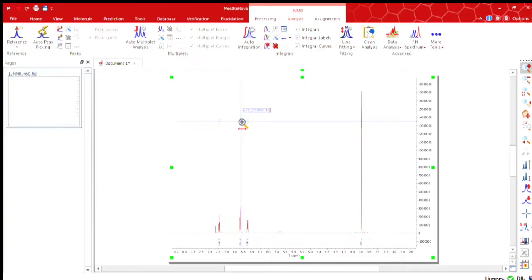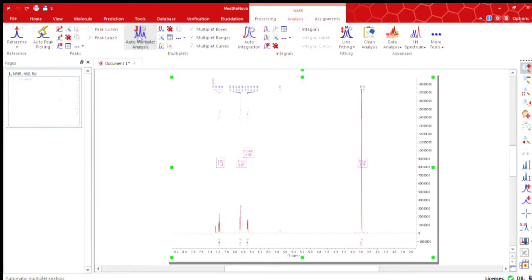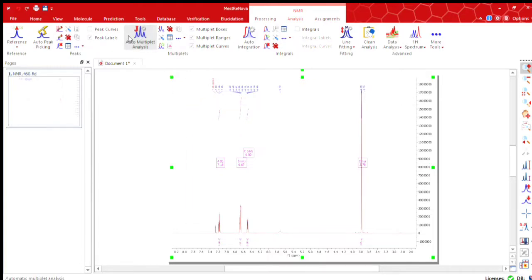Now, what we need to do is we need to find the J value of this integrated peak. So this is the sign to find the J value. As we press on it, we can see that the J value for the peak appears on the screen.